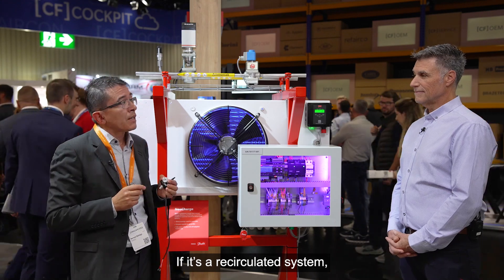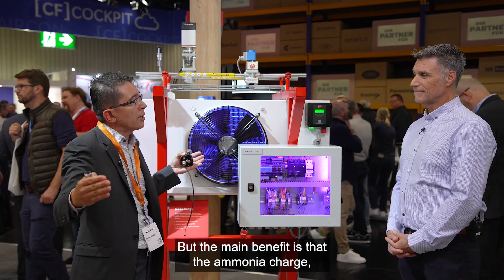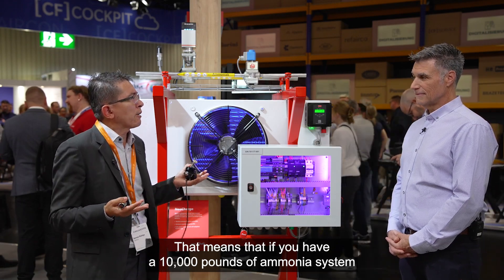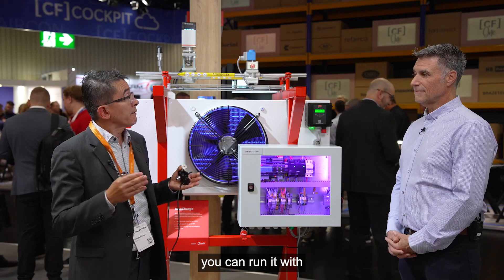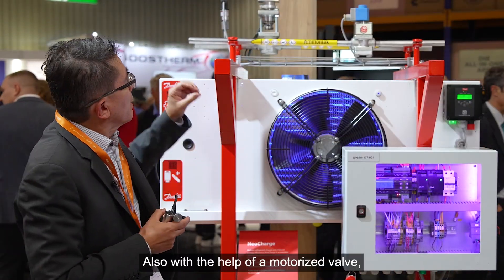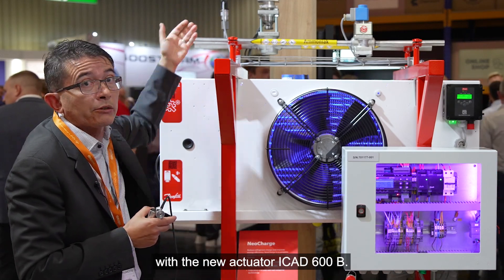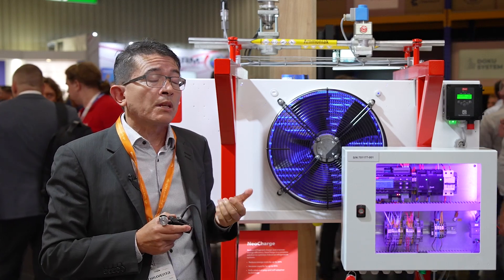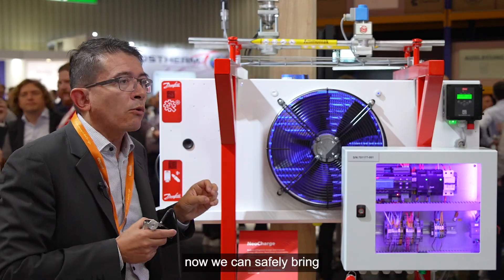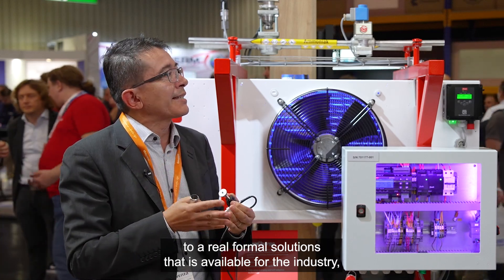If it's a recirculated system, then the energy efficiency improvement could be probably 2 to 3%. But the main benefit is that the ammonia charge at any given time would be reduced by 40%. That means that if you have a 10,000-pound ammonia system, you can run it with 6,000 pounds, reducing 4,000 pounds — that's remarkable. The technology is available today, also with the help of a motorized valve. The controller basically modulates the motorized valve with the new actuator ICAD 600B, which has a much higher resolution and is also fully connected via Bluetooth and Modbus connectivity. With all this in place, we can safely bring a real, formal solution that is available to the industry.